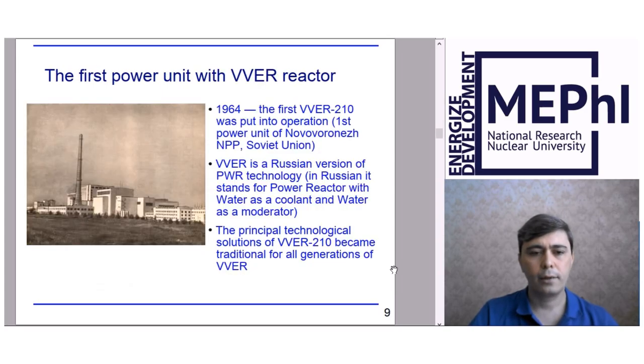But the water of the secondary circuit is at approximately 220 degrees at the inlet of the steam generator, with pressure not so high, approximately 6 or 7 megapascals. Of course, water of the secondary circuit, after contact with the hot tubes carrying water of the primary circuit, just evaporizes, and we have steam. As usual, in a thermal power plant we had steam after the boiler; now we have steam after the steam generator. The steam goes inside the turbine and rotates the generator. So the idea is to replace the boiler with equipment like the reactor vessel with nuclear fuel, and so on.